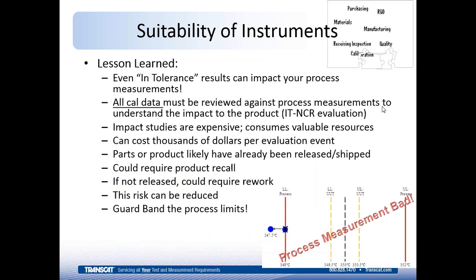So even in-tolerance results can impact the process. All cal data would have to be reviewed against the process measurements to understand whether there was an out-of-tolerance indication that would require nonconformance review.